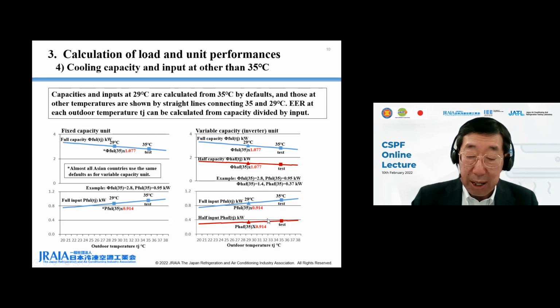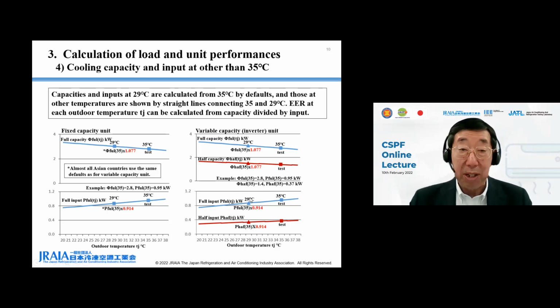Capacities and inputs at other temperatures are shown by straight lines connecting the values at 35 and 29 degrees C. Accordingly, full and half capacities and inputs can be calculated from 35 degrees C values multiplied by functions determined by Tj. Although EER is not shown in the figures, EER at each Tj can be calculated from the capacity divided by the input at each Tj. Next, please.